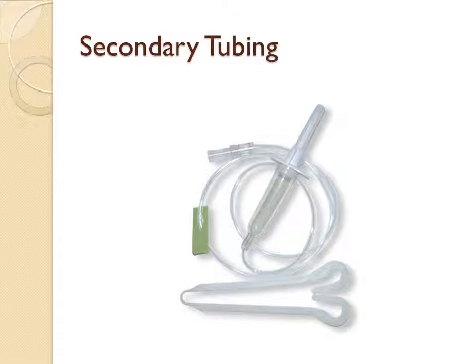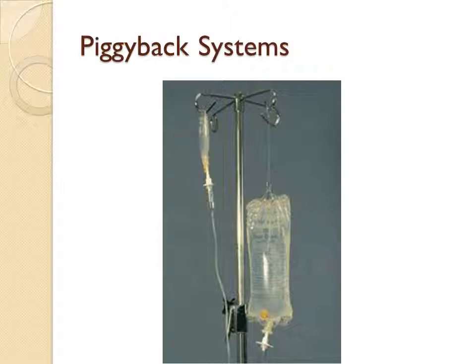This is a picture of secondary tubing. It consists of a drip chamber. It may have an auxiliary clamp of some kind, a needle attachment with a Luer lock, and a hanger. Make sure that the auxiliary clamp is closed prior to initiating priming the tubing. Piggyback systems have your mainline IV fluid, and unless it's placed on an infusion pump, it's infused by gravity. The higher the bag, the faster it will flow. Whatever bag is placed highest will infuse first. And you can see some backflow if the bag level is not appropriate.